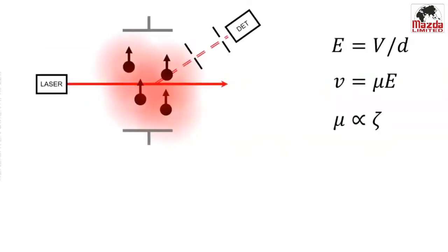So let's look at electrophoretic light scattering. If we shine a laser beam through a sample of particles, each particle will scatter the light and create a Doppler shift dependent on the velocity of that particle. It's like a police radar speed trap. And if you have millions of particles, then you have millions of Doppler shifts all contributing to the intensity of the scattered light. This varies with time in a similar way to a sound signal.